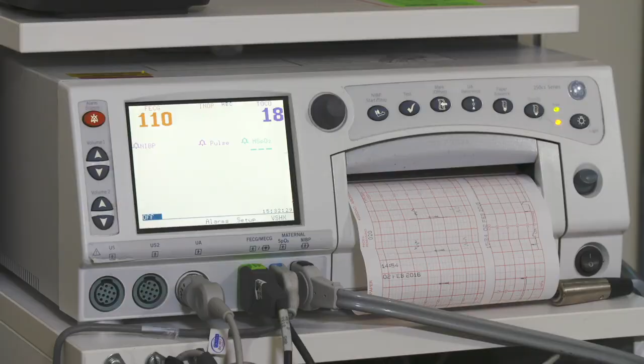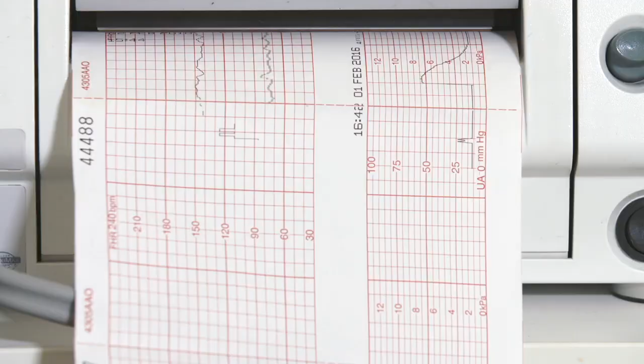Training Session 5. Monica trace identifiers and how long before monitoring commences. As soon as the monitoring screen is displayed on the Novii interface, you will see and hear what looks and sounds like FHR and UA pickup from the fetus and mom. It is not. The Novii interface sends an FHR and UA signal to the monitor that traces an M in the FHR and UA trace to identify the source of the FHR and UA. There will then be a short gap before the true MHR and UA are displayed. The FHR could take a little longer.